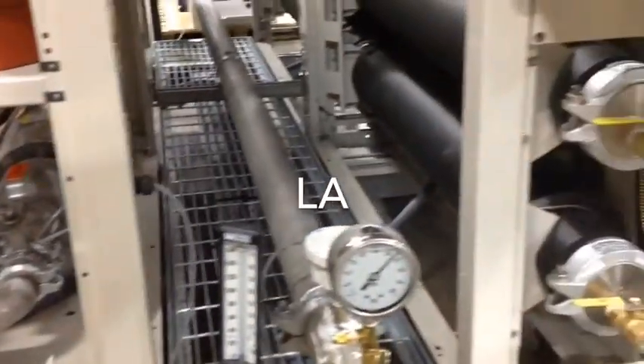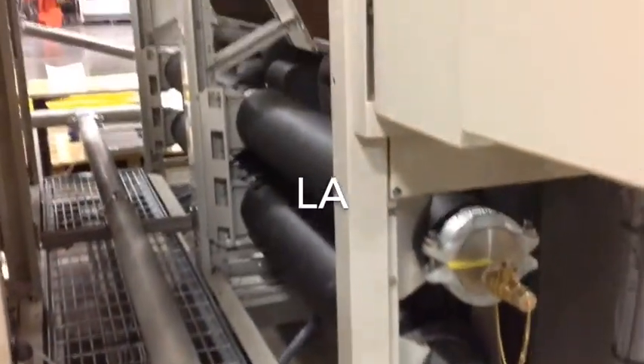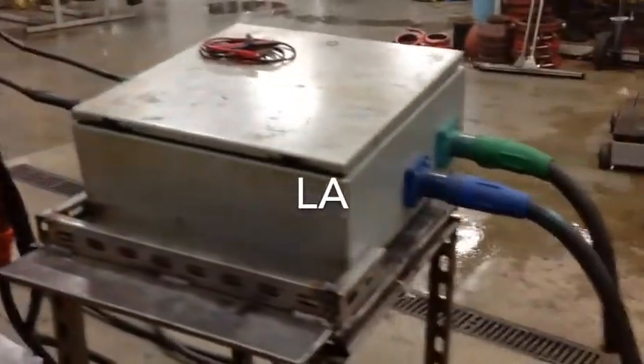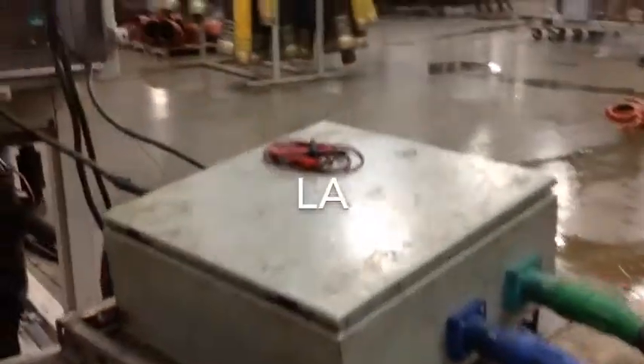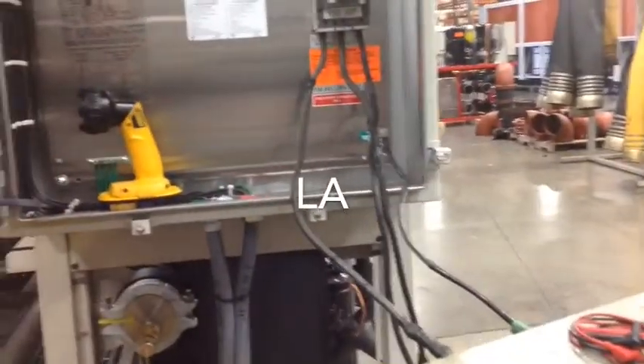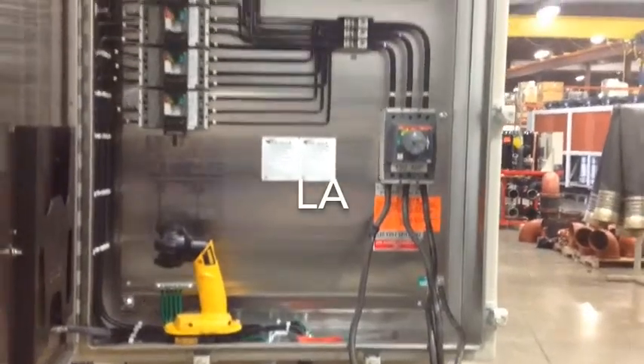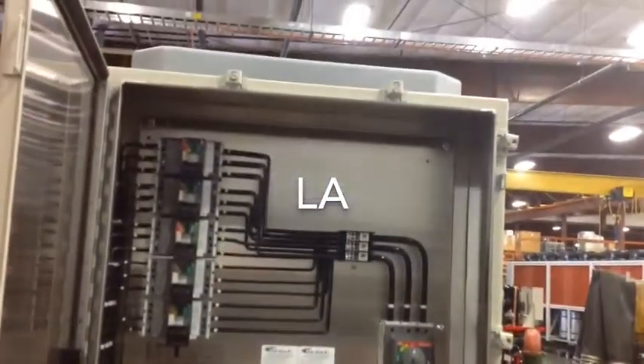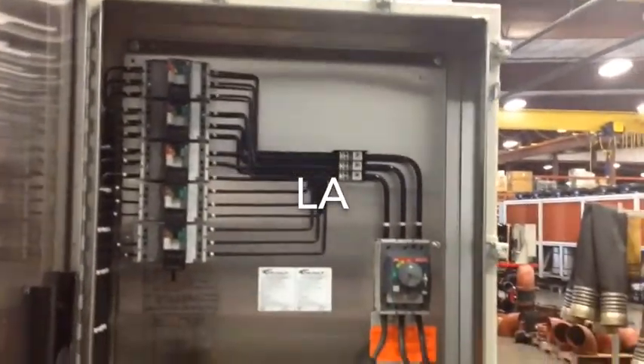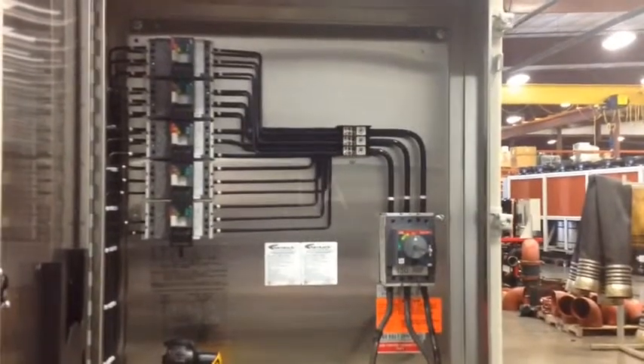A view of the connections from the expansion tank coming down there. This is the leaving pipe coming through the walkway, and now we'll swing over. This is the setup we used at the factory for phase loss testing, and now the junction box. 5 module breakers, 3, 1 for each mechanical module, 1 for the pump module, and 1 that feeds the C1 panel and the circuit breaker. Just a note here that there's 1 Carel controller in the master module.